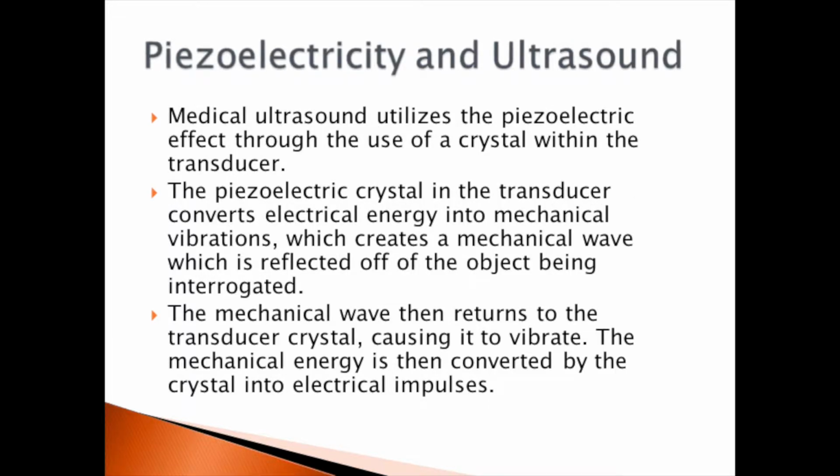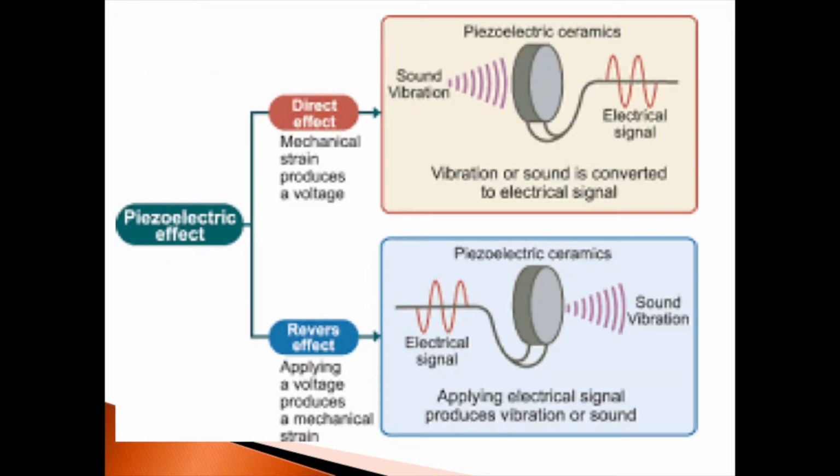Piezoelectricity and ultrasound. Medical ultrasound utilizes the piezoelectric effect through the use of a crystal within the transducer. The piezoelectric crystal in the transducer converts electrical energy into mechanical vibrations, which creates a mechanical wave which is reflected off of the object being interrogated. The mechanical wave then returns to the transducer crystal, causing it to vibrate. The mechanical energy is then converted by the crystal into electrical impulses.